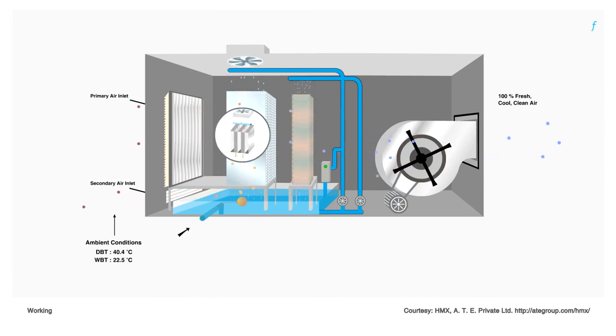Warm air entering the wet air stream panel of the heat exchanger from the secondary air inlet becomes warmer as it gains some heat while vaporizing water off the wet surface of the panel. Air coming from the primary air inlet is cooled while passing through the cooled heat exchanger panels. This completes the first stage or the indirect stage.